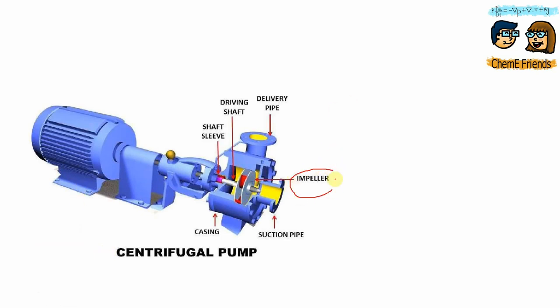Let us see the main components of the pump. First, the impeller — it is a rotor which is used to increase the kinetic energy of flow. Then, casing — it can be of two types: volute and vortex. Casing contains the liquid and acts as a vessel that directs the flow of liquid in and out of the pump. Then, the shaft — the impeller is mounted on the shaft and it is connected to the external source of energy. Delivery pipe — it is connected at its lower end to the outlet of the pump and delivers the liquid to the required height. Suction pipe — it is used to transfer the fluid from the source to the pump.